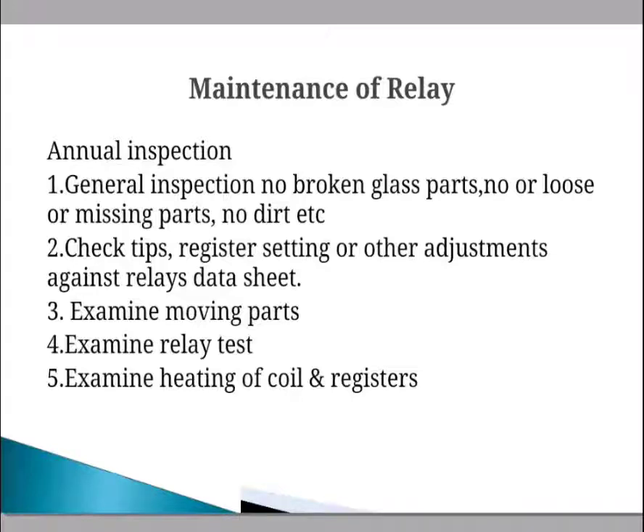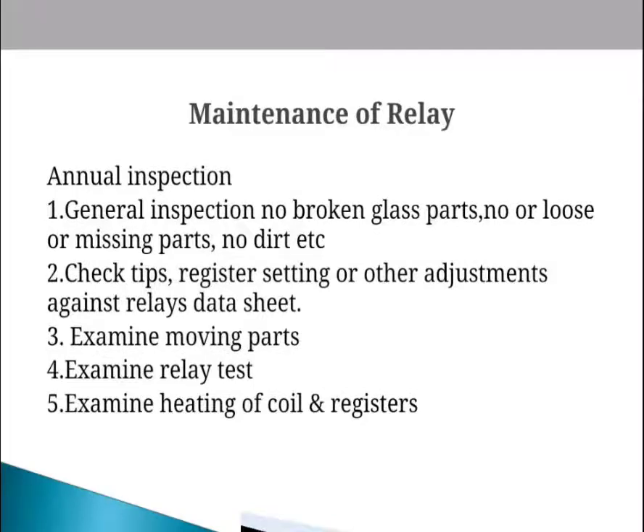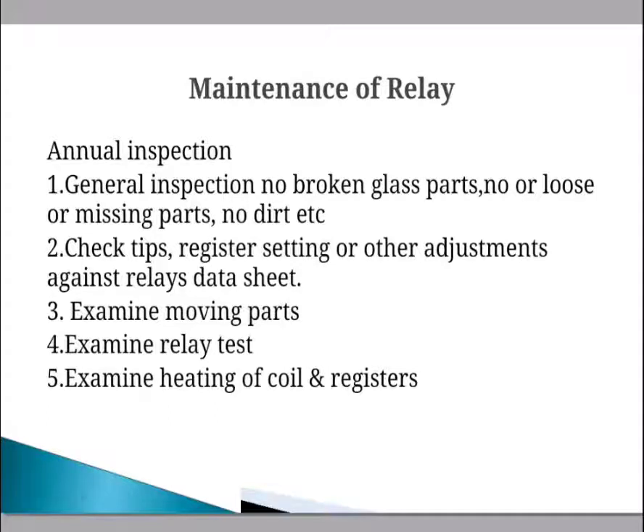In the annual inspection, we have to check the general condition: no broken glass parts, no loose or missing parts. We have to check for dirt or decomposition on the relay and clean it. Check the trip settings and other adjustments against the relay data sheet.